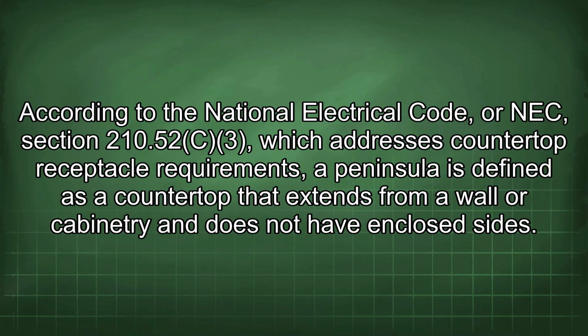According to the National Electrical Code, or NEC, Section 210.52(C)(3), which addresses countertop receptacle requirements, a peninsula is defined as a countertop that extends from a wall or cabinetry and does not have enclosed sides.